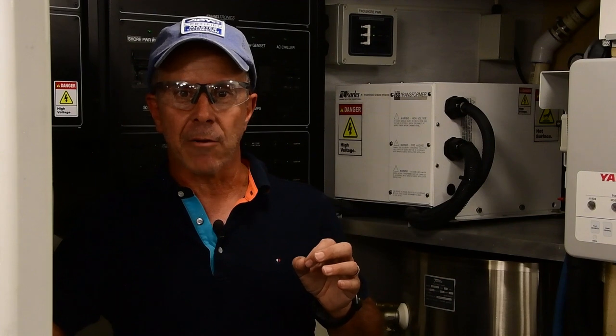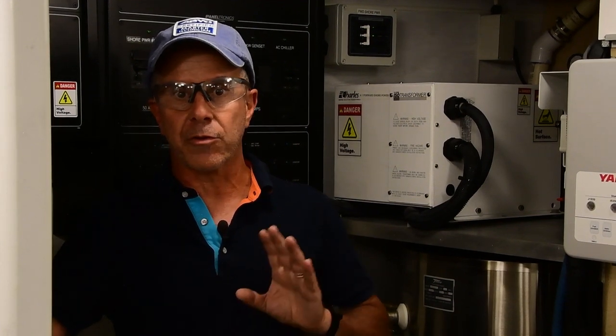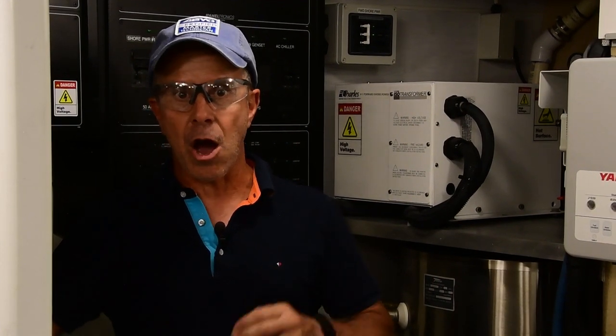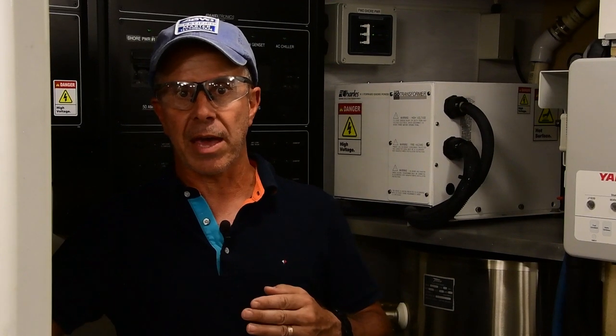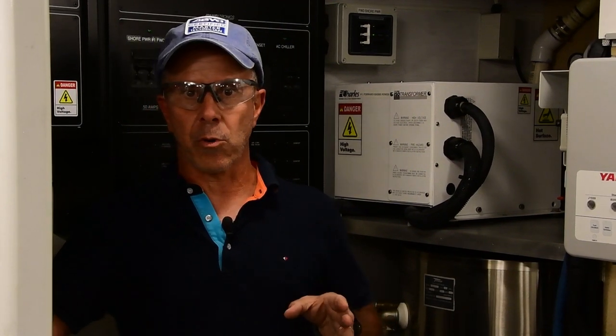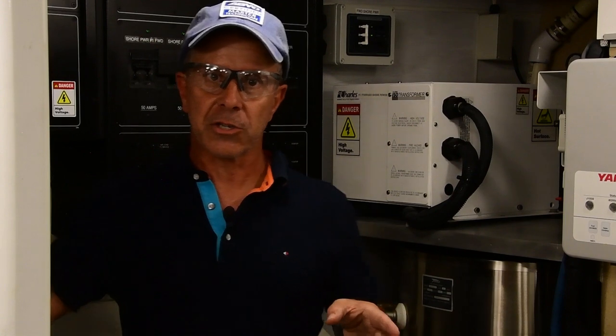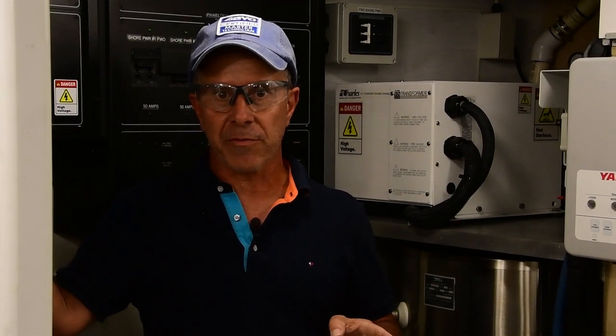So ironically, you are almost better off with no transformer than a non-boosting transformer because of that 208, 104 scenario. On a dock that is 208, if you don't have a transformer, you're going to get 208 and 120. If you do have a non-boosting transformer, you're going to get 208 and 104 on the boat. So again, if you're considering investing in a transformer, I absolutely recommend that it be a boosting variety of transformer.